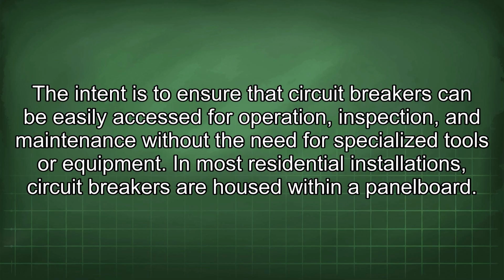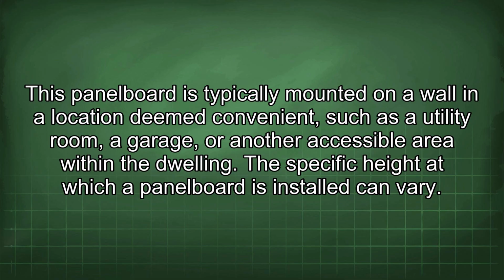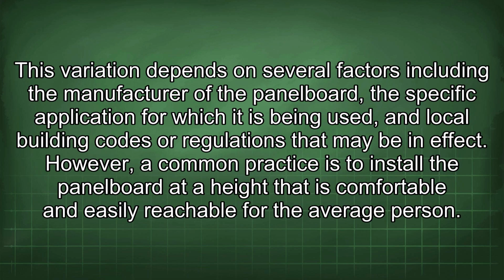In most residential installations, circuit breakers are housed within a panel board. This panel board is typically mounted on a wall in a location deemed convenient, such as a utility room, a garage, or another accessible area within the dwelling. The specific height at which a panel board is installed can vary. This variation depends on several factors, including the manufacturer of the panel board, the specific application for which it is being used, and local building codes or regulations that may be in effect.